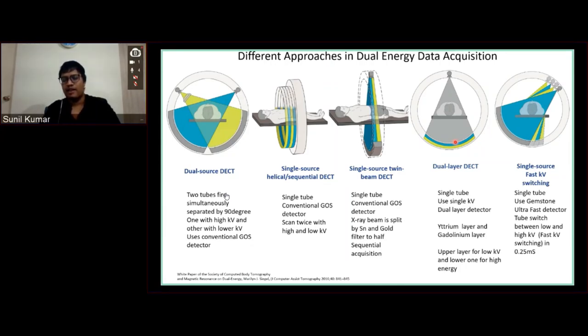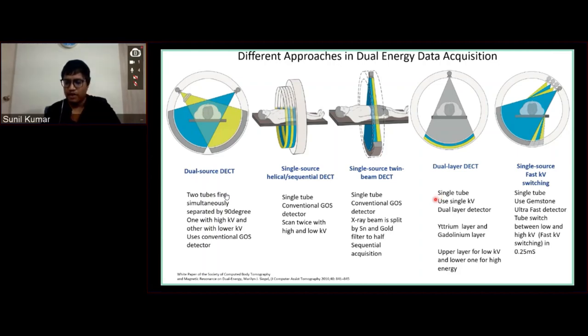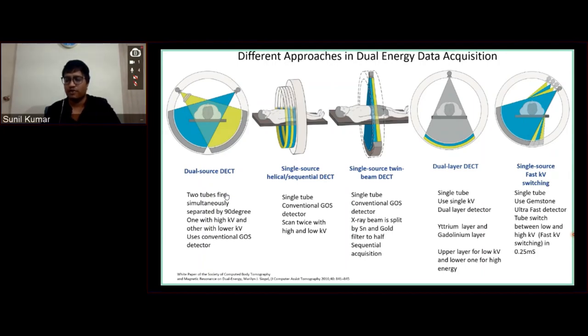Now we have the most trusted and reliable source — and of course it's from GE. This is the unique feature we follow, and none of the other vendors have it in the market right now. The first change is in the detector: while all other detectors so far are made of gadolinium, we use something called the Gemstone Spectral Detector. It has high spatial resolution and very low afterglow — essentially zero afterglow — which is very, very important.